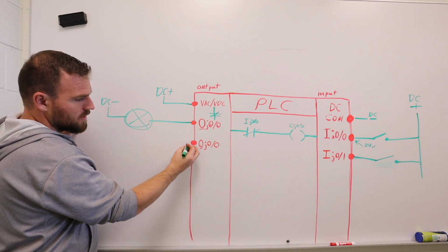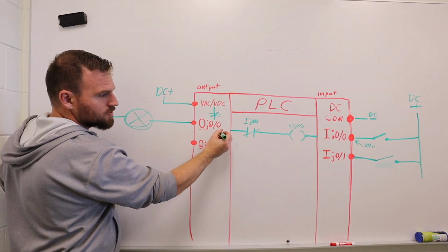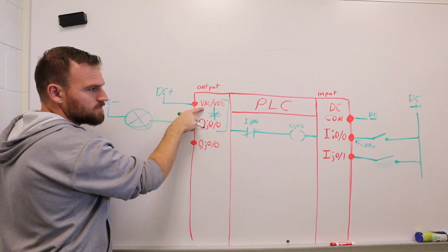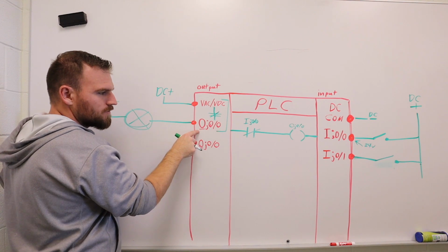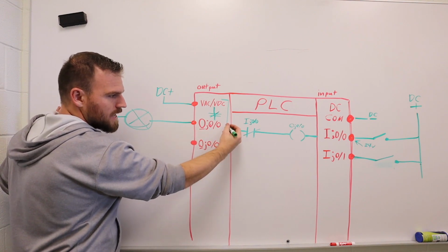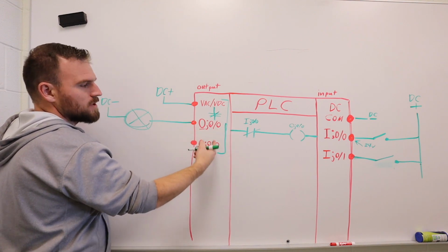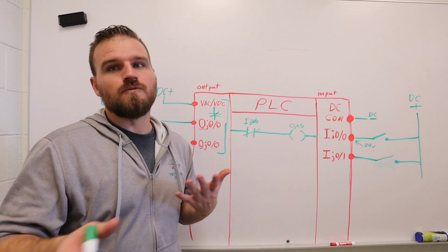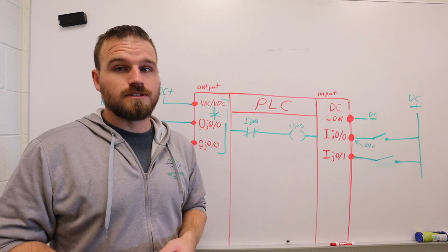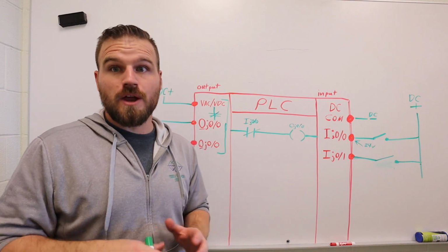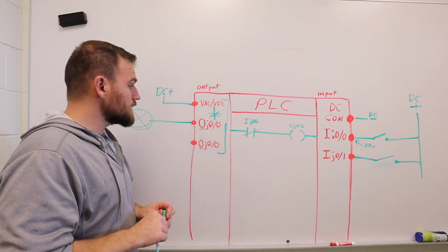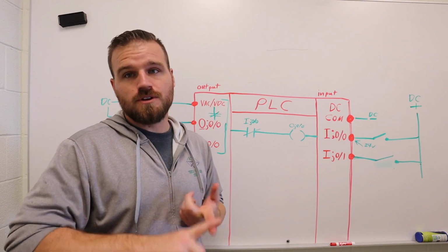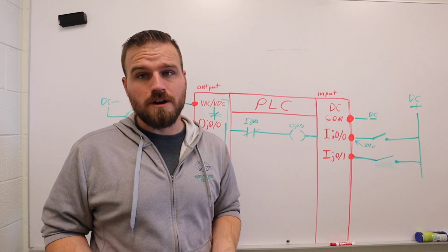One thing you're going to see is there's going to be a bracket over each one of these. Now, it's saying this VAC / VDC is only good for this terminal. If this bracket extends onto another one, then these two are supplied voltage here. It's made that way so we can have multiple voltages being used on one PLC. So you can actually get pretty tricky with some of that stuff, all right? So let's go ahead, and what I want to do is show you those terminals on that PLC, and then I'm going to show you the schematic, and then I'm actually going to show you it wired, okay?